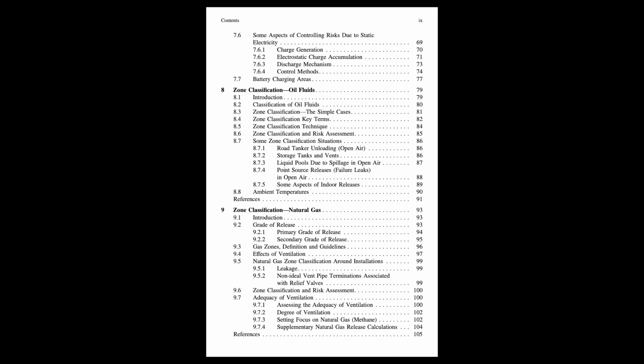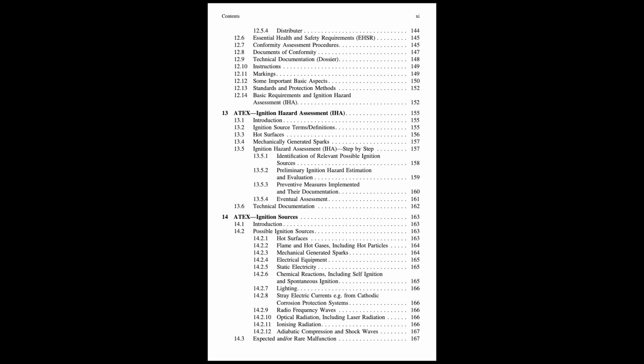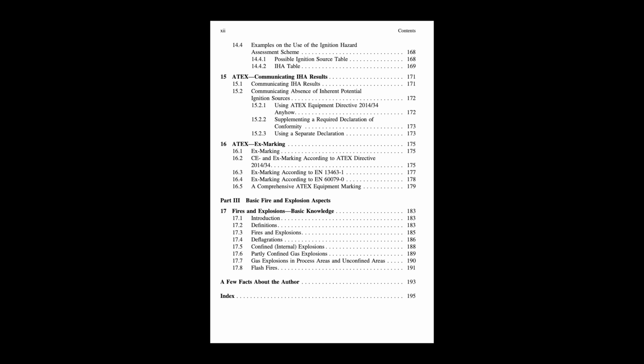The second is explosion-resistant design, sometimes called explosion containment. So instead of venting it, you just build the equipment super strong. That's the idea. You design and build the equipment robustly enough to withstand the maximum pressure generated by an internal explosion without rupturing. It might deform slightly, but it contains the blast. Makes sense. When would you use this? It's often more practical and economical for smaller volume equipment, where the cost and weight of making it that strong aren't prohibitive. Trying to contain an explosion in a massive silo, for example, would be extremely difficult. Okay, build it strong enough.